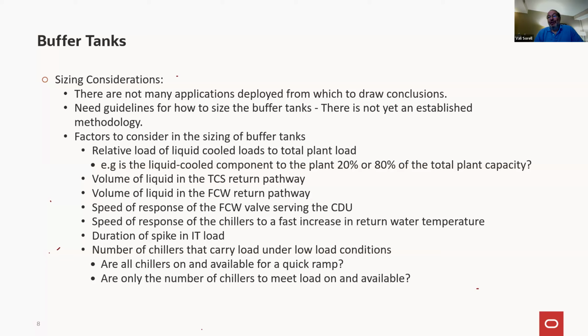Actually, it's exactly the point that I was trying to come to. So I suggested to a certain designer doing this for me how to do this in a spreadsheet. And I think I scared them away, only because it seemed like there were a lot of loose ends they would need to figure out to make a valid model. I think it's easiest to do it in a spreadsheet. You could do it as thermal response, looking at every second or every 5 seconds, and you just keep adding load to a thermal mass as the flow continues out from the IT to the cooling plant. I would know how to do it. I have not set up that spreadsheet.